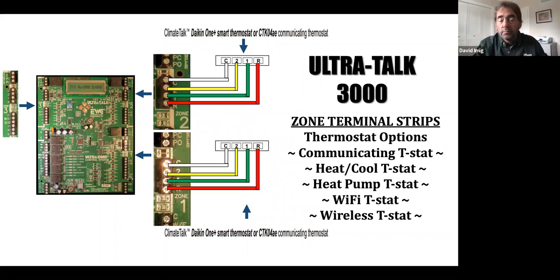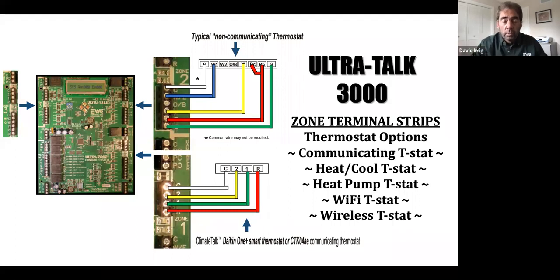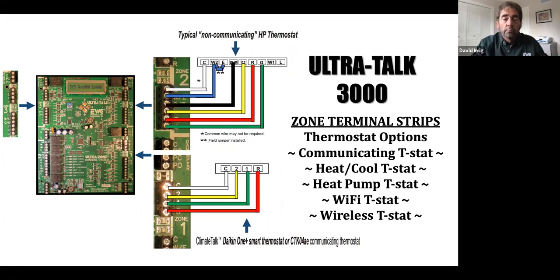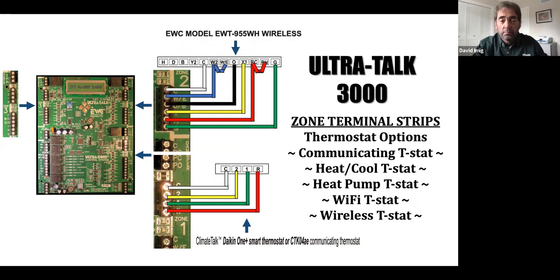If we look at the thermostat terminal, and these are the different options that are available, you'll see that I can accept multiple options at thermostat. I do not have to use a Daikin One in all zones. It is recommended, and highly recommended, that you use a Daikin One stat in zone 1. If you look at some other examples here, I've got a non-communicating heat-cool stat in zone 2. I'm utilizing a heat pump stat in this particular example, a Wi-Fi stat, and the wireless stat, all with the Daikin One stat in zone 1.